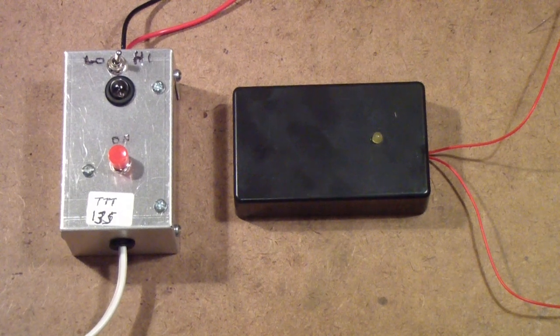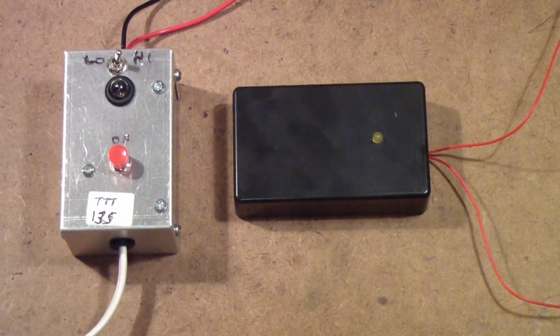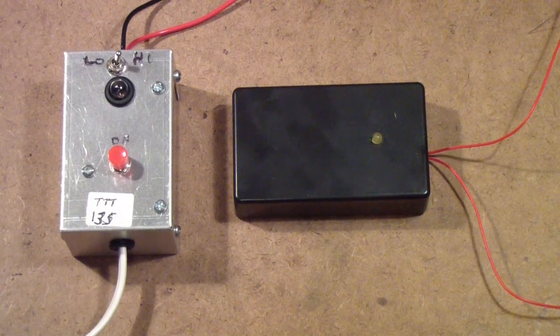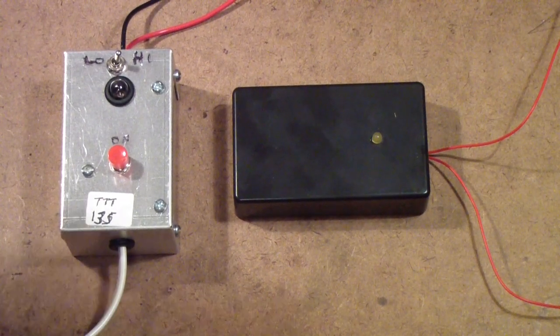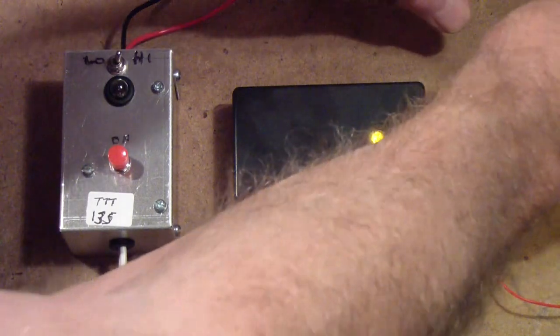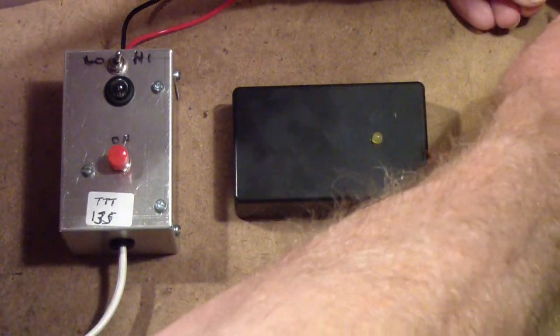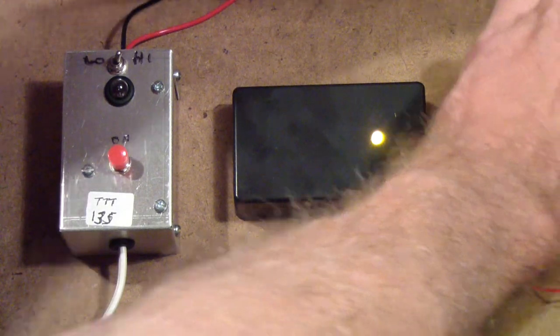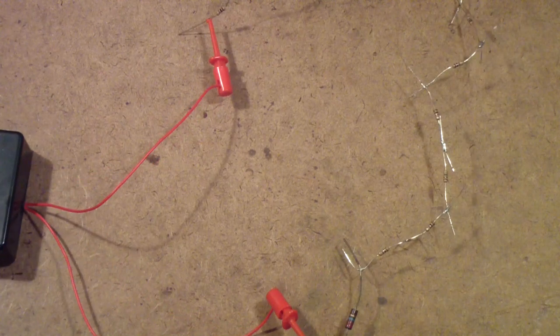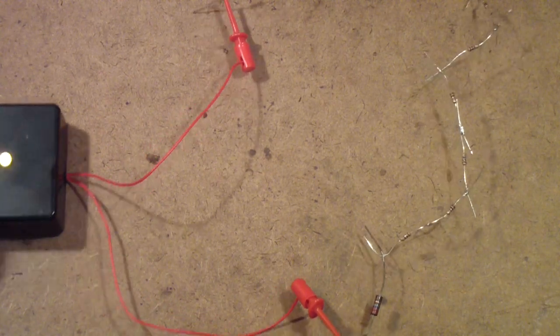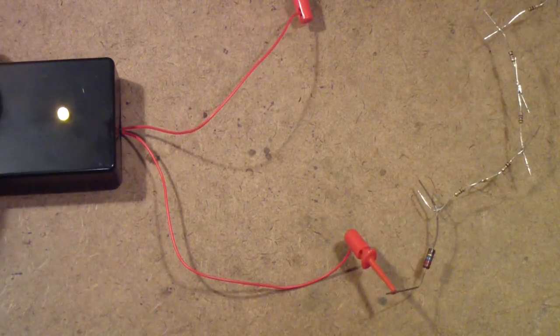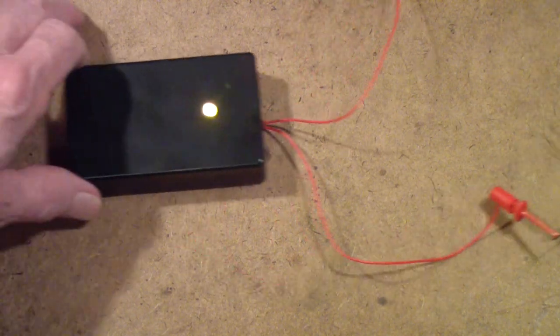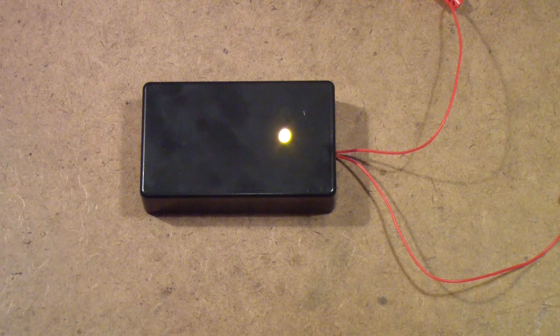So let's take a look at these circuits and then I'll, oh, by the way, let me, here is the tester. And you see what I'm doing there is I'm testing it on a string of resistors. I think this is about 150 mega ohm. And you see it, it definitely will show 150 mega ohm of leakage.